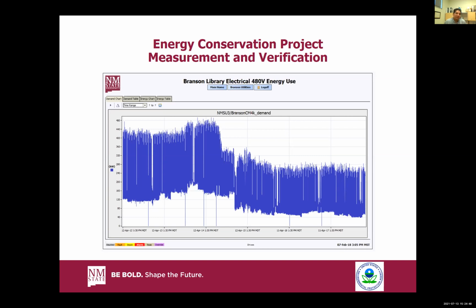So this is an example of data provided from an electric meter at our Branson Library building. We did a lighting conversion from fluorescent T12s—they didn't quite go to LED on this project, this was done in 2014, but we did go to T5 fluorescents. As you see the pattern of the graph here, we're running around 440, 450 kilowatts before the project. And we can see just about midpoint of that graph where we have a substantial drop. So this proves to us that the lighting conversion caused a substantial drop in energy consumption.